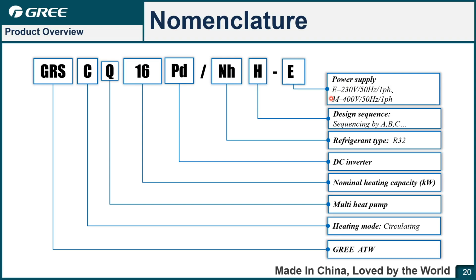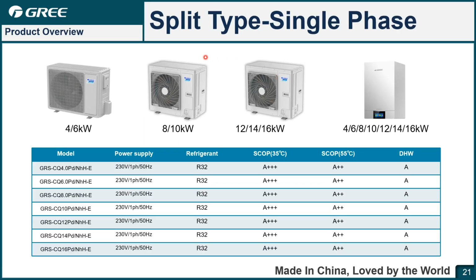However, for North America, the power supply is different. So in future, we can get the corresponding model for the North American market, and you can still use this one in your market. So for the split VERSATI 3 single phase, the capacity ranges from the minimum 4 kilowatts, 6, 8, 10, and the maximum can be 16 kilowatts. And they share the same hydro box.